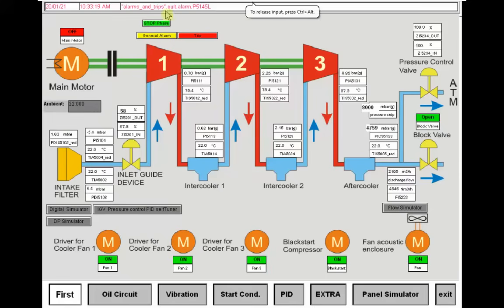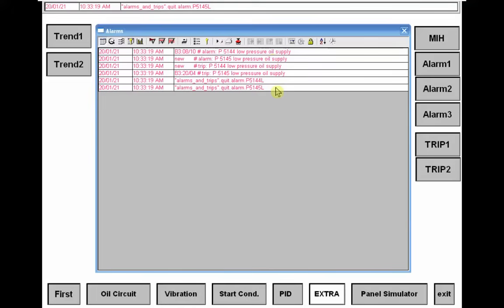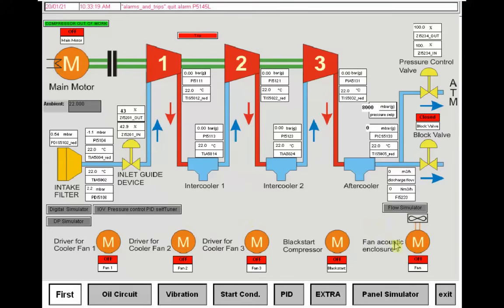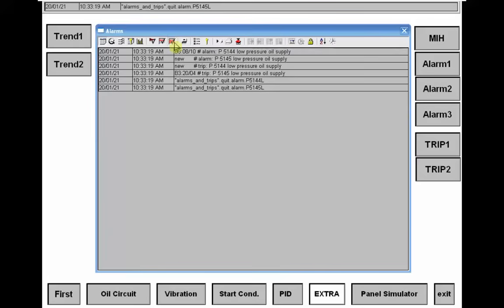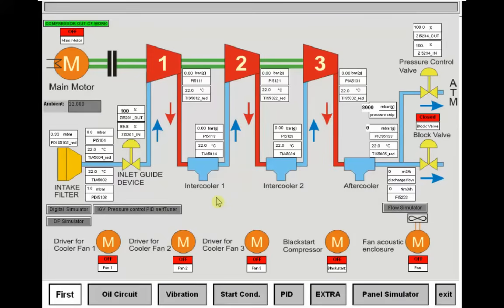Let me apply the changes here. You can see that the main motor is tripped and the compressor is also tripped. The cause of trip is pressure low, related to the oil pressure transmitter. So it's possible to see all the signals here related to the oil supply — that is the main protection related to the compressor. If the compressor is in run mode and we lose the pressure related to oil pressure, the compressor will be shut down for safety. That's the function test here.